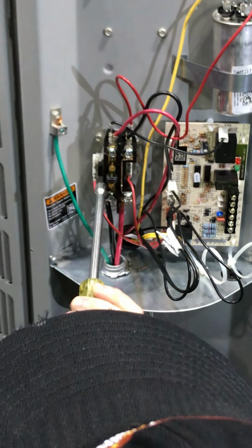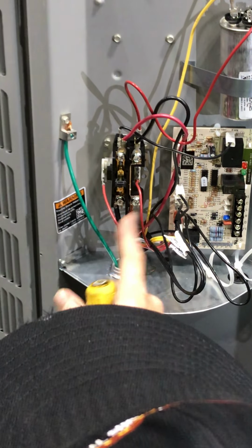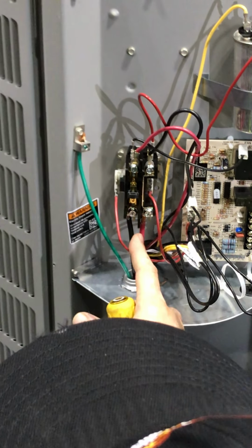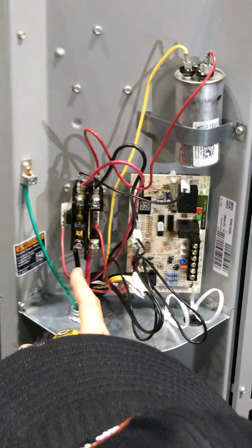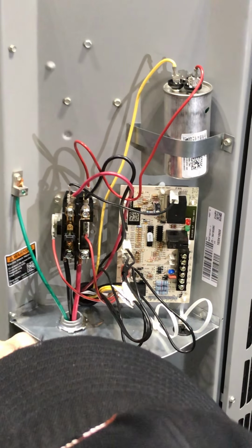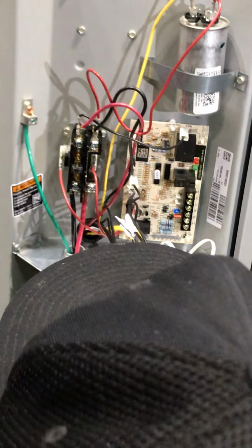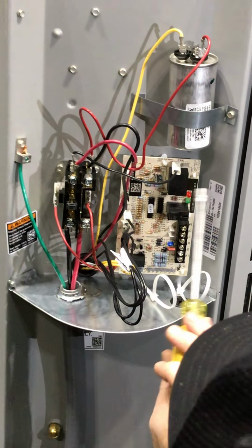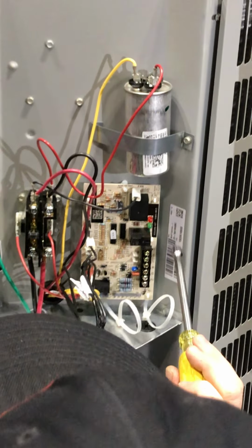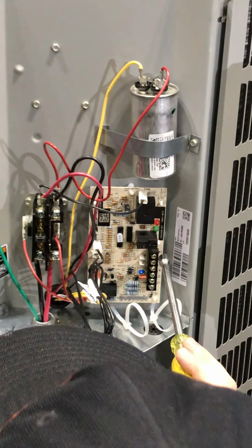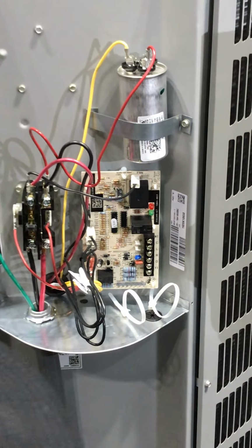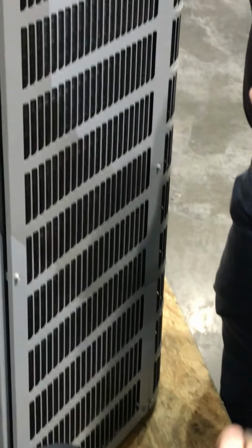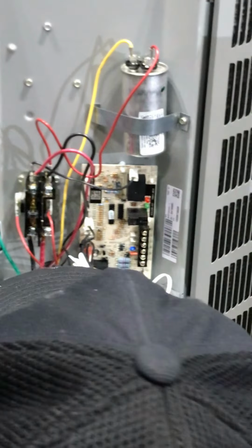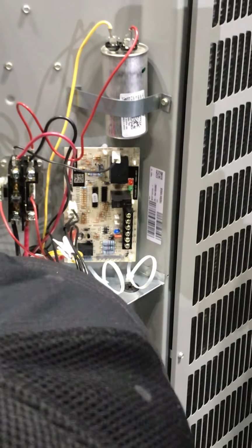If this is not engaged, and I go over here and engage it, and everything turns on, my problem is my 24 volts, which go where, Richard? To the thermostat. Nice. So this is going here, which zigzags around with all these controls to my thermostat. So it could be as simple as tightening one of these down. Or I have to check my thermostat wire. Maybe that got hit by a weed whacker, or maybe a kid was running by and tripped over it and popped one of these wires out, or maybe over time and corrosion, it just went bad.